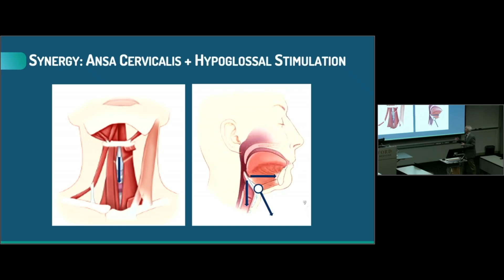And the pilot data are shown here, again from Dave Kent, in the next slide, showing that cross-sectional area is represented on the right-hand panel here. Ansa cervicalis stimulation alone, that's the cross-sectional area, about 200. Hypoglossal alone, maybe a little less than 200. But combining the two, generally speaking, leads to an improvement in the overall patency of the airway. And that improvement can also be reflected by the bump up with combined stimulation and airflow compared to just hypoglossal stimulation alone. That's the left-hand panel.